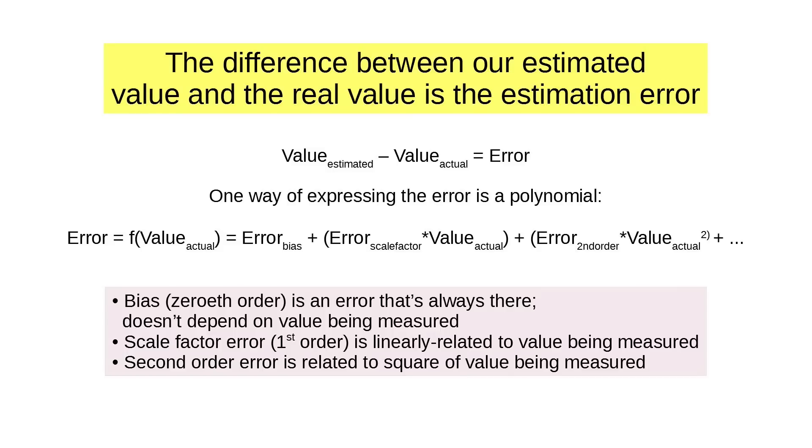The bias or zeroth order, it says zeroth because it's the value to the zeroth power, which is just one. It's an error that's always there, like that stupid minus one amp measure on the power supply. The error doesn't depend on the value being measured. In fact, the power supply is off. The scale factor error is linearly related to the value being measured. So as the value goes up, the error goes up. A second order error is related to the square of the value being measured. Let's just take a look at some pictures. It's a lot easier.